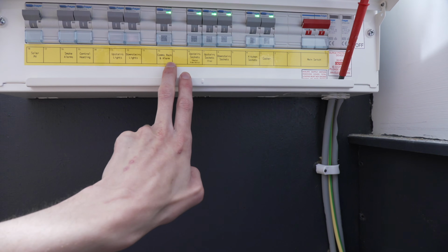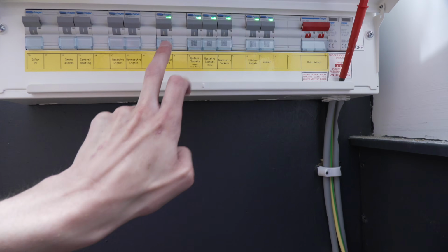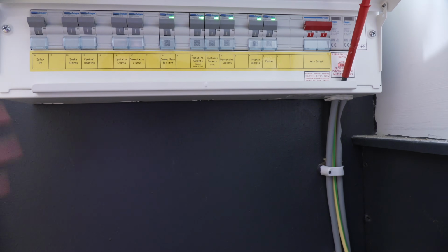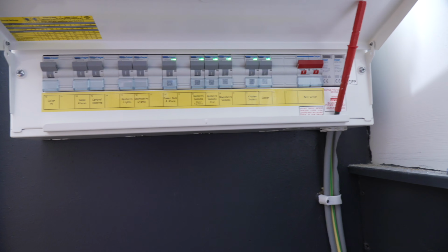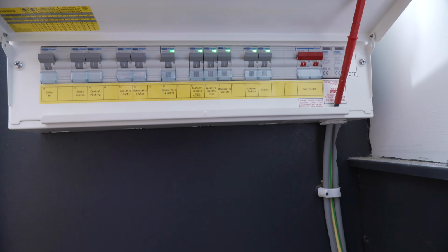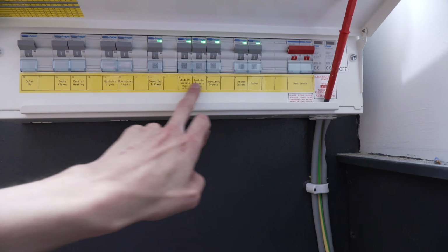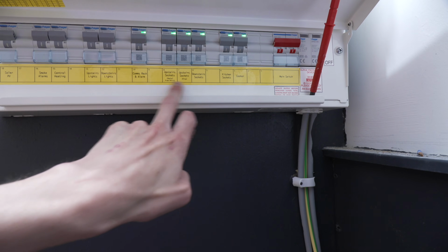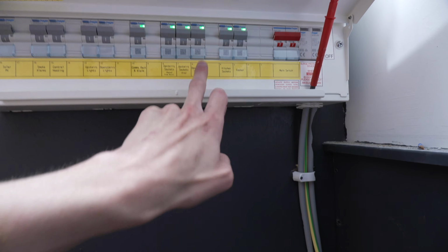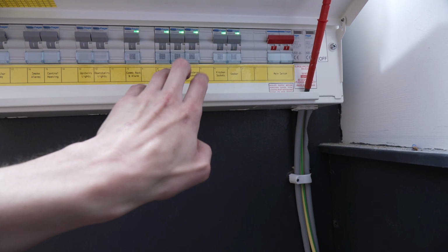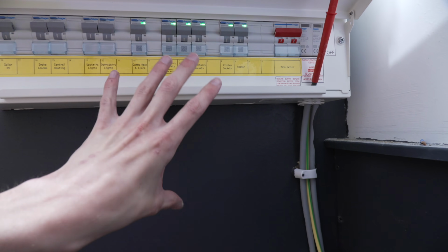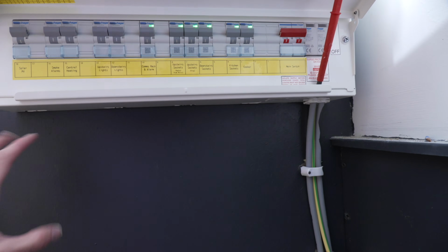We have one for comms rack and alarms, that's my comms rack. I'm going to monitor that on its own, because that's the whole comms rack, audio system, CCTV, anything that's powered over Power over Ethernet is done through this. Then we have 3 separate socket circuits, so two upstairs socket circuits and a downstairs socket circuit. I'm going to monitor those on one CT, so I'll have one CT just monitoring general sockets.